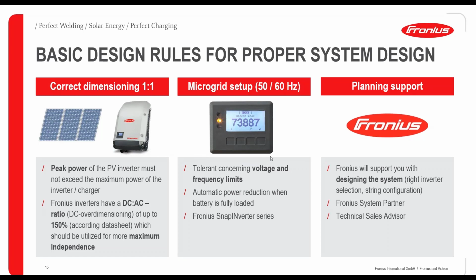We have this microgrid setup in 50 and 60 Hertz, pre-installed at the Fronius inverter, which you have to choose. It's tolerant concerning voltage and frequency limits, and is necessary to realize this frequency-controlled power reduction and frequency controlling via Victron.